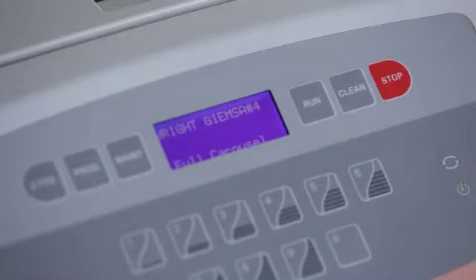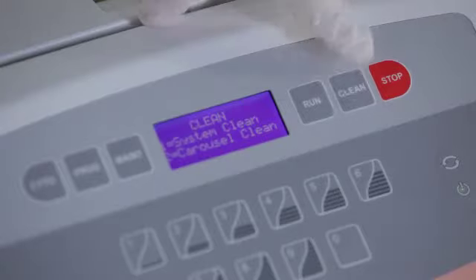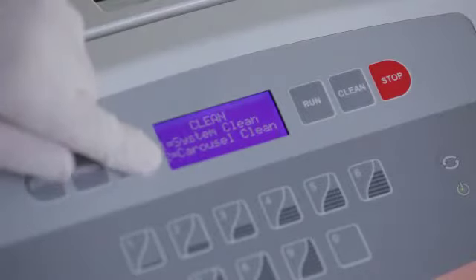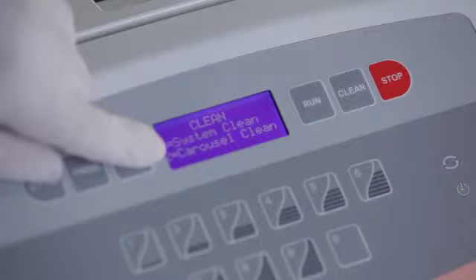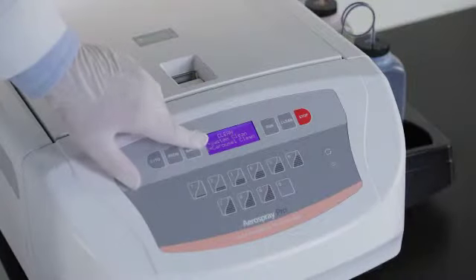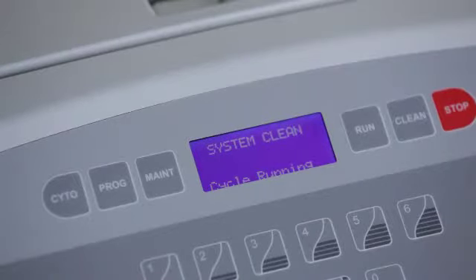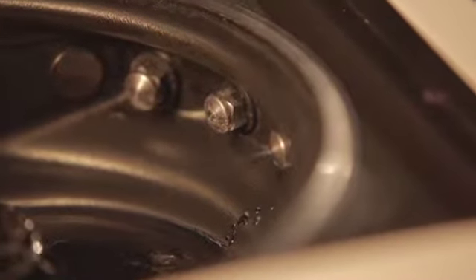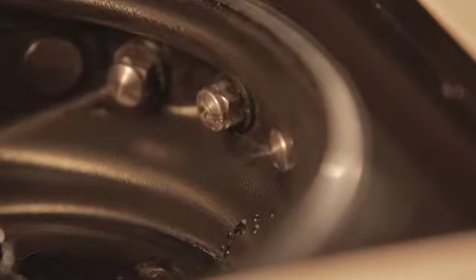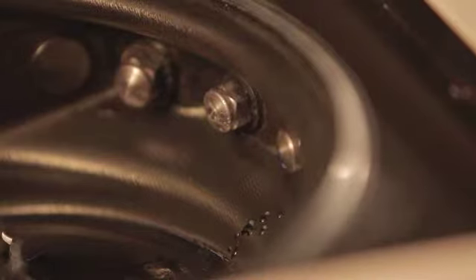The clean cycle on the Hematology Pro Stainer is different from the other Aerospray stainers. This stainer has 2 clean cycles, a system clean and a carousel clean. Both of these clean cycles spray methanol through the lines of the stainer, which keeps the nozzles clean. The carousel clean sprays more methanol than the system clean cycle. It is used to keep the carousel cleaner. There are no reprime cycles for either of these clean cycles. At the end of each stain cycle, methanol is sprayed out of the nozzles. This helps keep the nozzles clean.